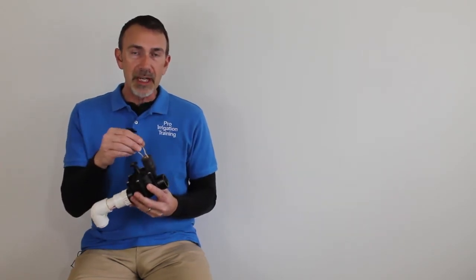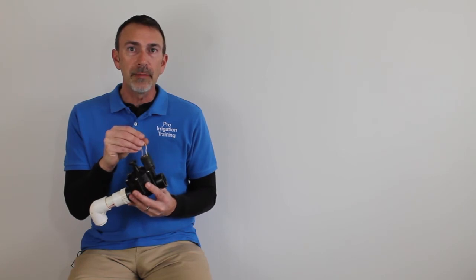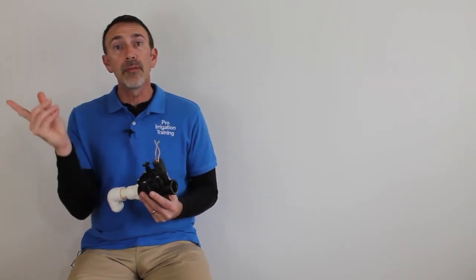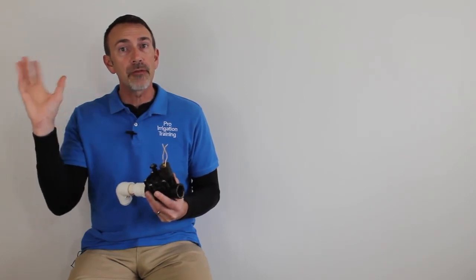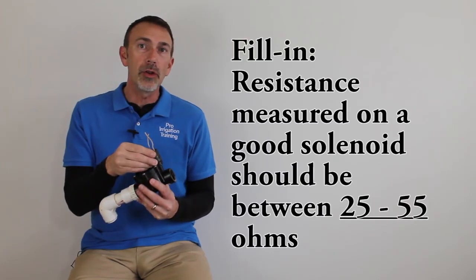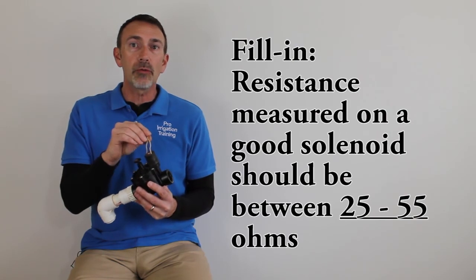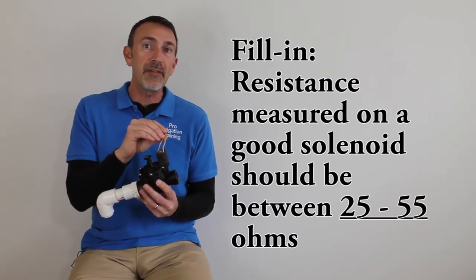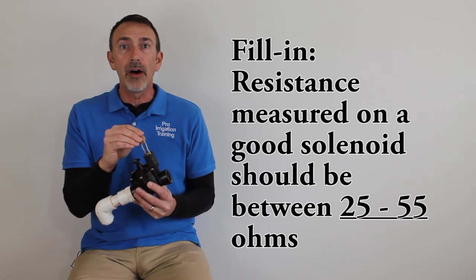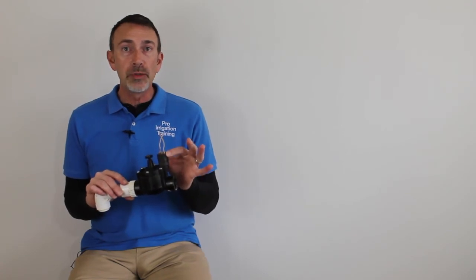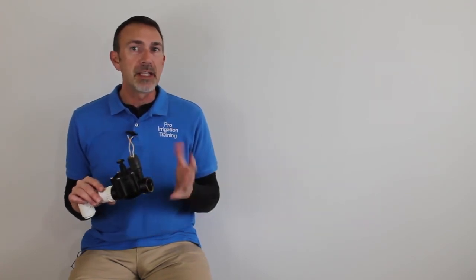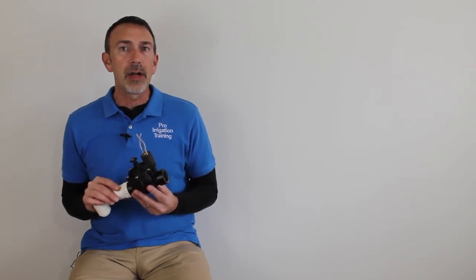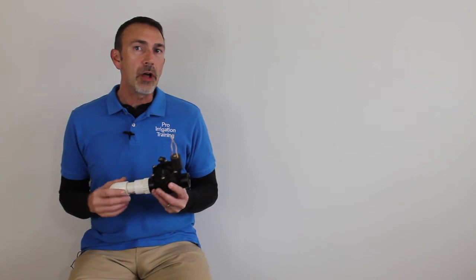Now when we measure the resistance on a solenoid, it can be measured here at the solenoid or from the timer, since we have a continuous circuit from the timer out here to the solenoid, and typically what you're going to read on a good solenoid is between 25 ohms and 55 ohms. And when we get down and talk about each individual valve, I'm going to give you the individual ohms that you should be reading for each manufacturer. Like I said, they're a little bit different, so you'll need to have these on hand as you go out and do troubleshooting on some valves.